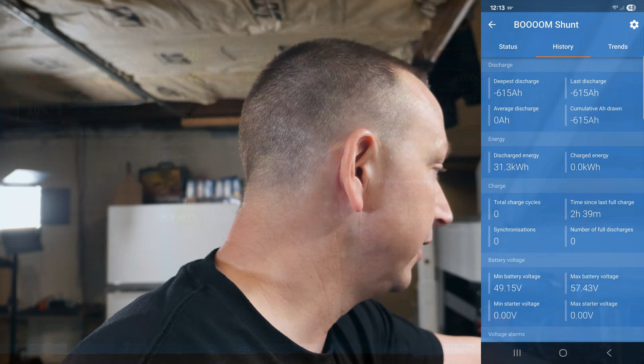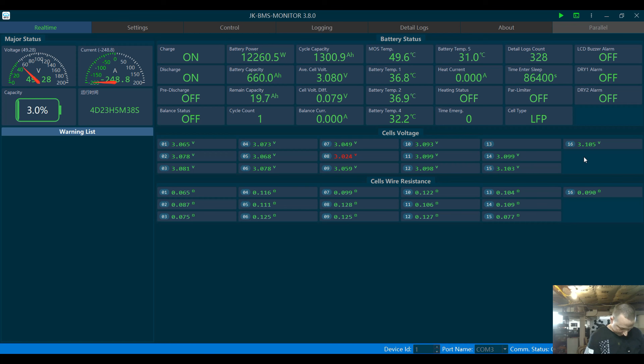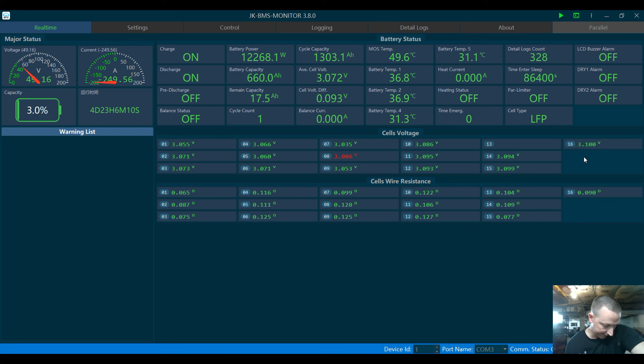Amazing. Cell differentials at 74 millivolts, and I would imagine, of course, that's going to climb the further we go down. So here in just a minute, I am going to lower the amp draw again. While I'm doing this, I'm just going to keep an eye on the temperatures down here. Fuse is at 232 degrees. The bus bar is at 180 degrees. Back of the circuit breaker is 127. Okay, going to drop it down just a little bit, back down to 247. Boom shunt showing 1%, 1 minute, 623 amp hour, 31.8 kilowatt hour.